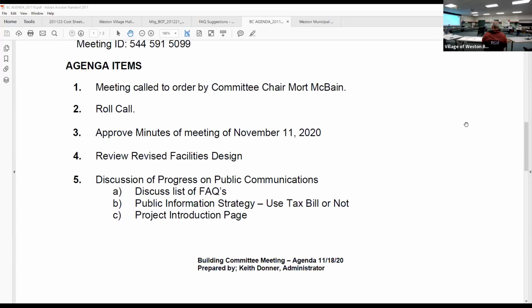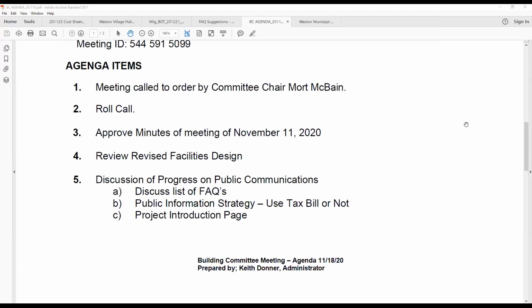Do you have an estimate about how much the controls are going to be on this system? The controls are a considerable part of it. We think you're probably going to need a BAS whether you have a VRF or a VAV system. I don't think we're even in the ballpark unless you have the energy recovery in your DOAS system - you're not even in the ballpark as far as comparison of energy.